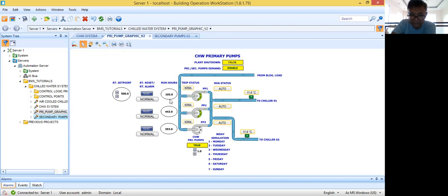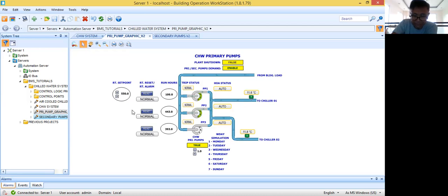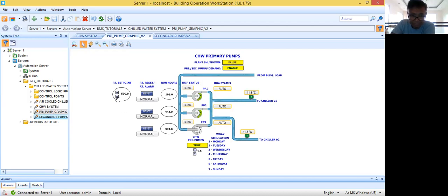When the pump reaches that setpoint, the system will raise a runtime alarm. I have here a reset and RT alarm button — so I have the reset and the alarm. All these alarms are currently normal. There will be a runtime alarm if the run hours of a pump are equal to or greater than 500 hours. To make it more flexible, I used increase and decrease step arrows here — I made it a 50-step increment, so every time you press the up arrow it increases by 50. So we can put it back to 500.